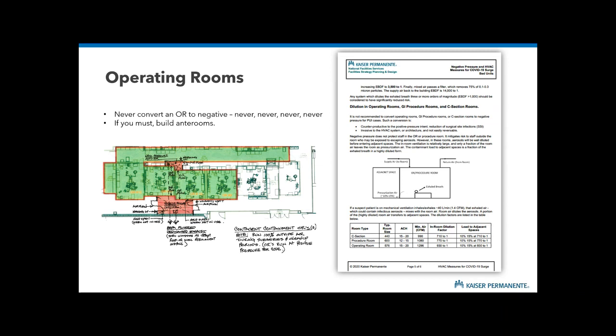We included this conversation about dilution ratio, and you can see it in the actual text of the white paper there. We called it EBDF, the exhale breath dilution factor. This is a concept that we frankly made up, but it was very, very useful in communicating to the doctors and to the staff leads. Here's how it works. Human breath is about 6 liters per minute, which is 0.2 CFM. The maximum setting on a breathing machine is about 40 liters per minute, which is 1.4 CFM.